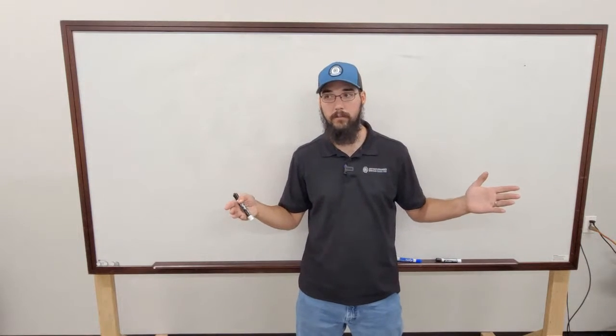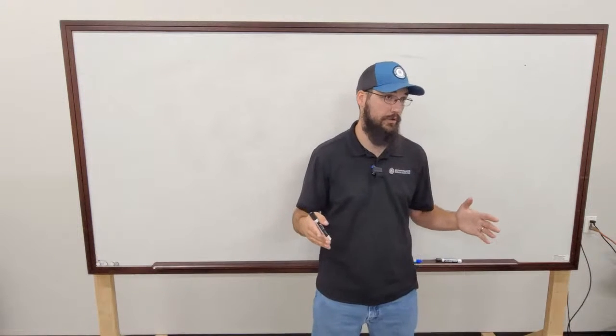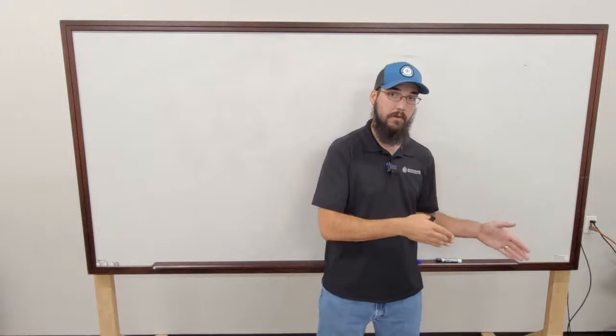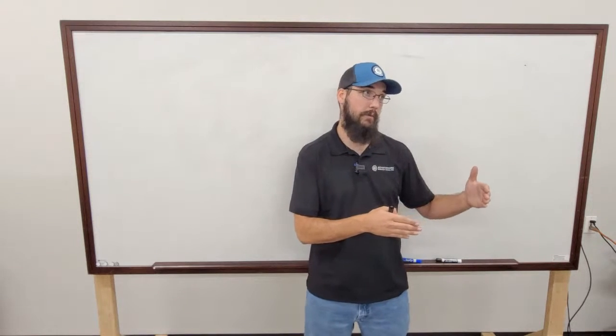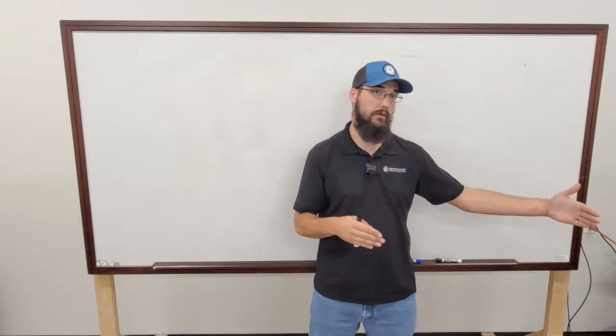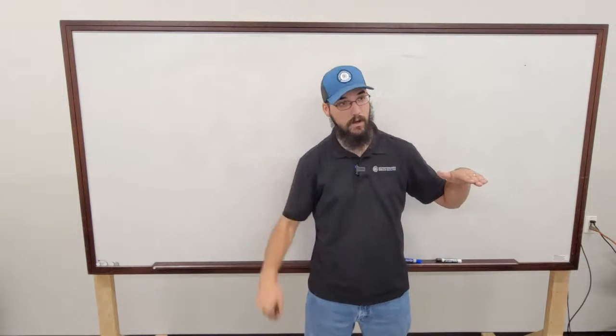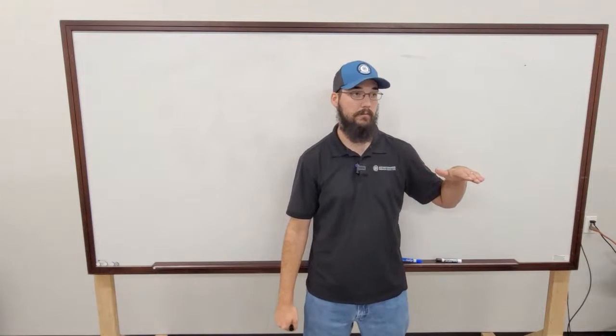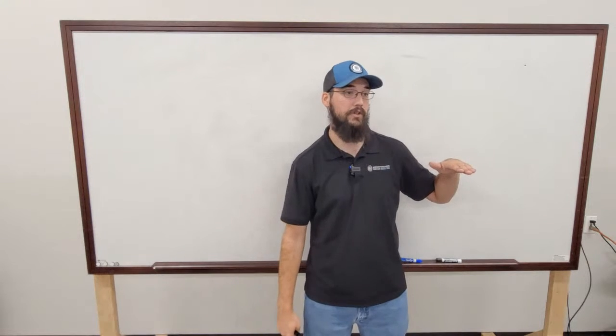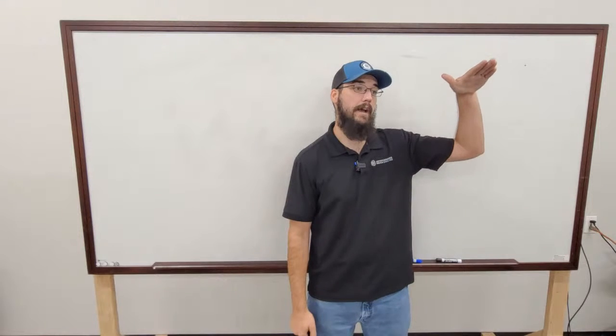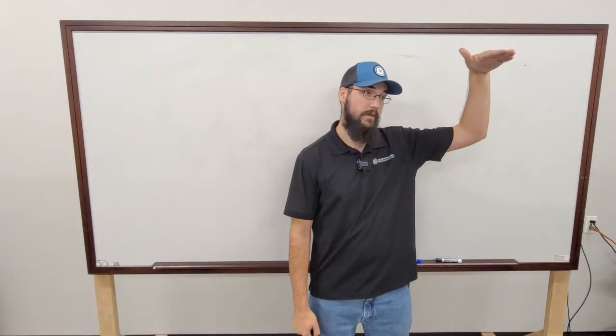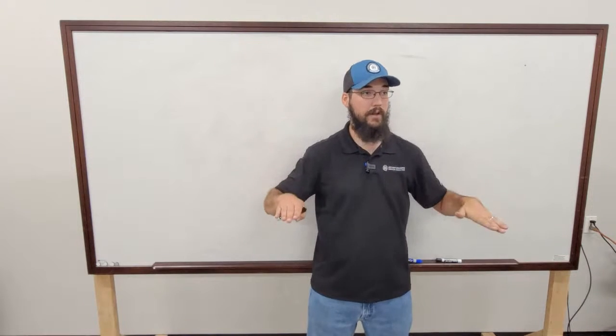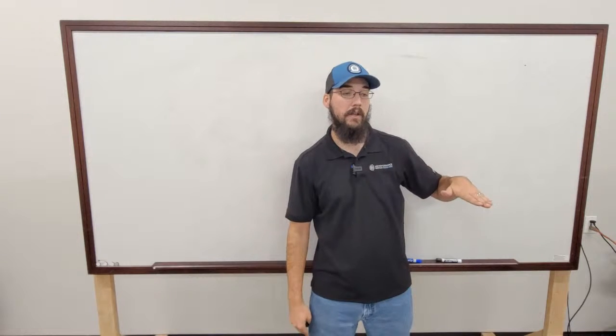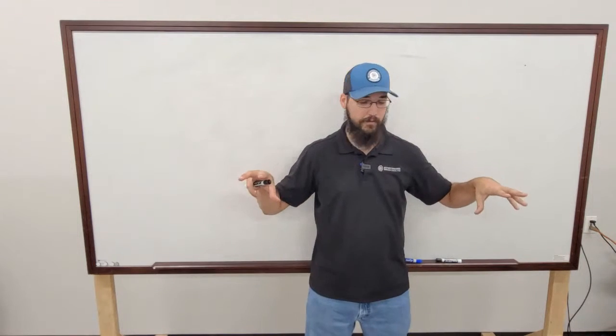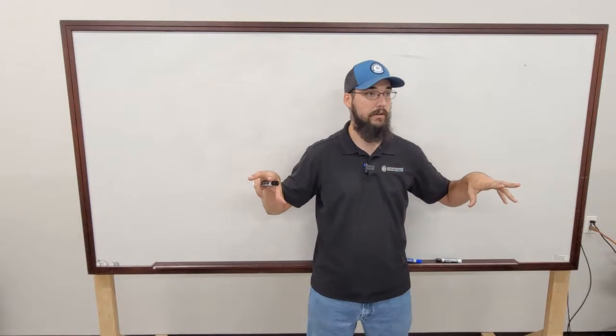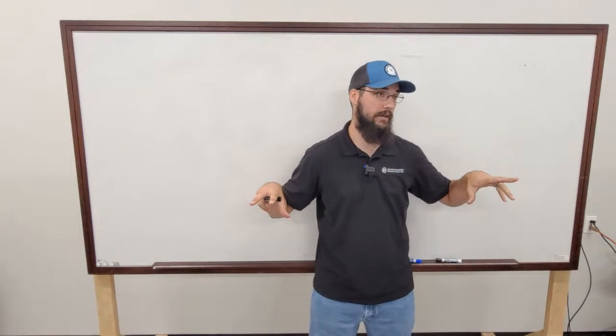So if our differential for shutdown or stop was 2 degrees, once we hit that 2-degree mark and we hold that mark for more than so many minutes or seconds, then it's going to drop out that lag circuit. So in this case, we'll say circuit 2. Circuit 2 is going to shut down, and then it's going to start to ramp circuit 1 back up to catch the load. Because the 2 of them together, both running at minimum, was too much, but we shut this one down. Now we can run where both of these couldn't unload past 30% each, but we needed just one of them to run at 40% to maintain load.